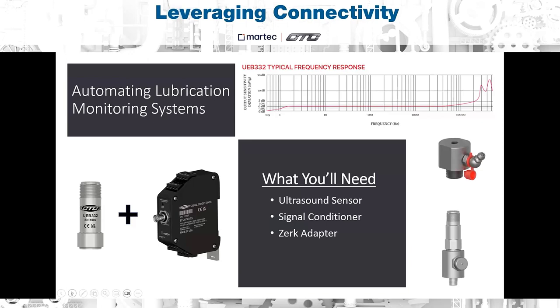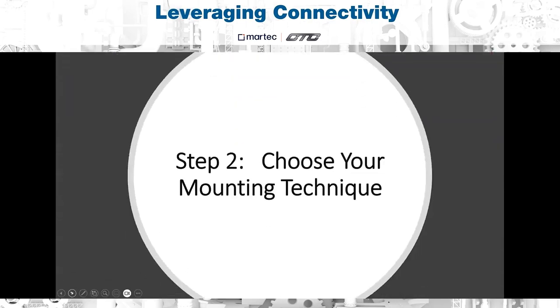That ultrasound sensor can also be paired with one of our Zerk adapters, which allows you to apply grease directly to your bearing, even while you're taking your reading, and you won't have to remove any component as it will be permanently installed, and you can connect your grease gun directly to that port on the Zerk adapter. So that is a general overview of things you need to consider and options you have when selecting a sensor. But the next step is to choose your mounting technique.